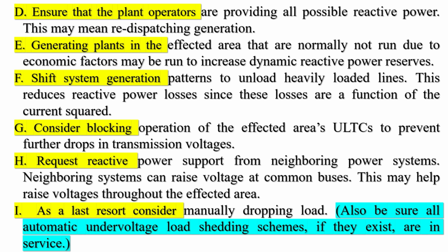This reduces reactive power losses since these losses are a function of the current squared. G. Consider blocking operation of the affected area's ULTCs to prevent further drops in transmission voltages. H. Request reactive power support from neighboring power systems. Neighboring systems can raise voltage at common buses. This may help raise voltages throughout the affected area. I. As a last resort, consider manually dropping load. Also be sure all automatic undervoltage load shedding schemes, if they exist, are in service.